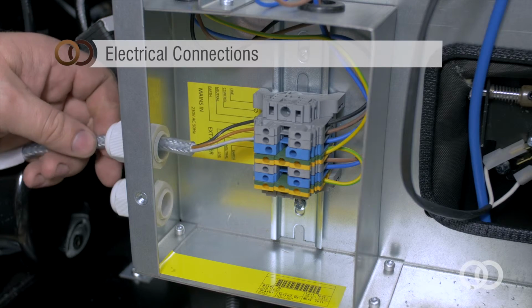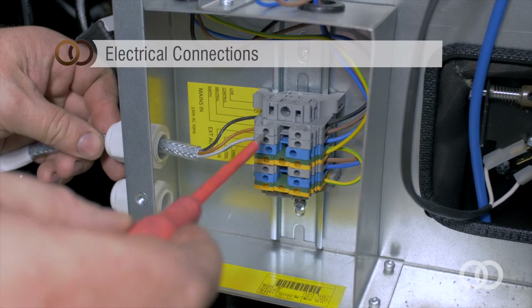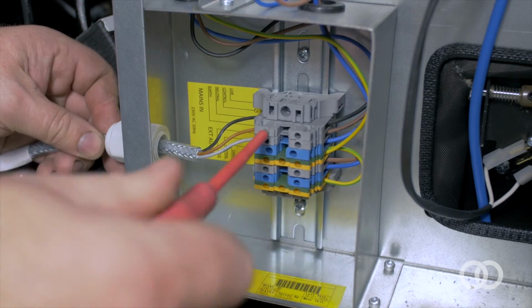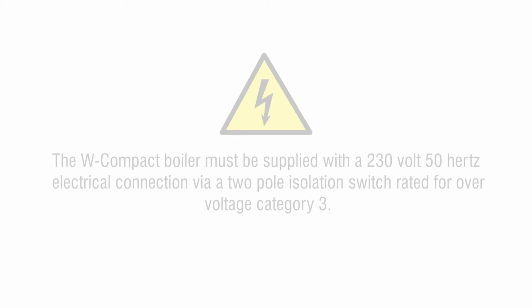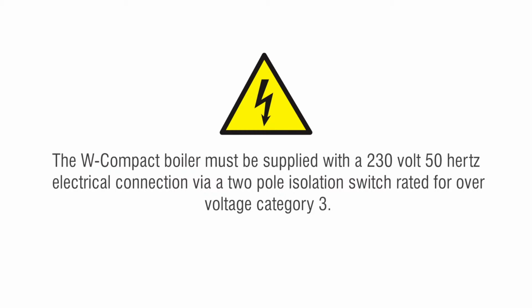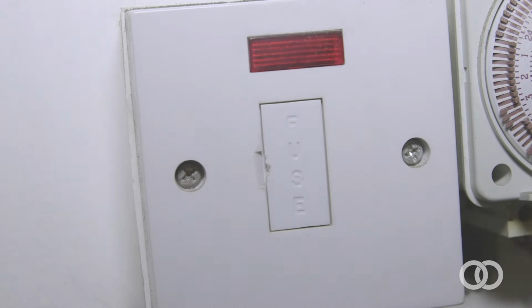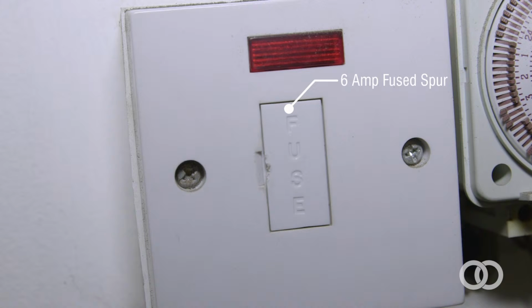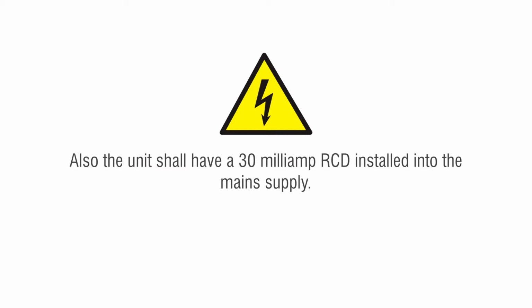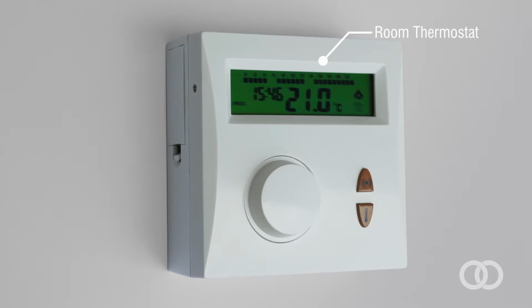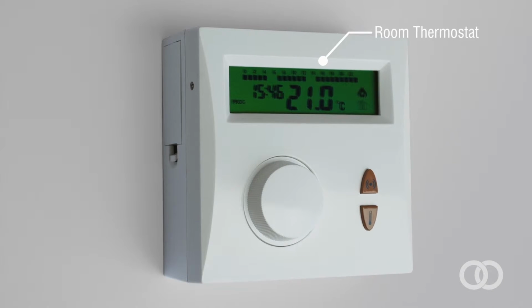Electrical connections. Ensure your electrician has the necessary qualifications and installs to the electrical standards in your country. The boiler must be supplied with a 230 volt 50 Hz electrical connection via a 2-pole isolation switch rated for over voltage category 3. It must be protected with a 6 amp circuit breaker. Also, the unit shall have a 30 mA RCD installed into the main supply. Room thermostat shall be supplied controlled by extra low safety voltage.